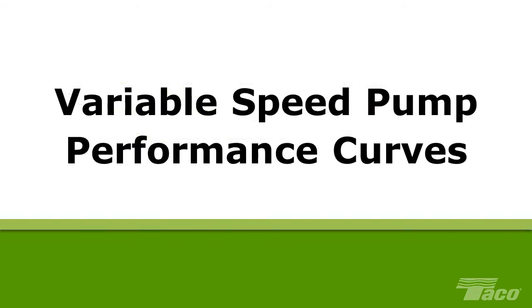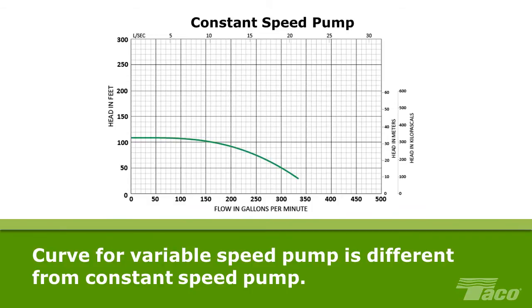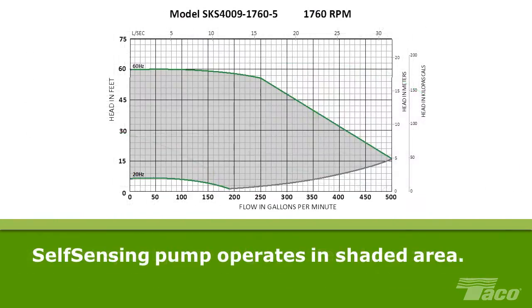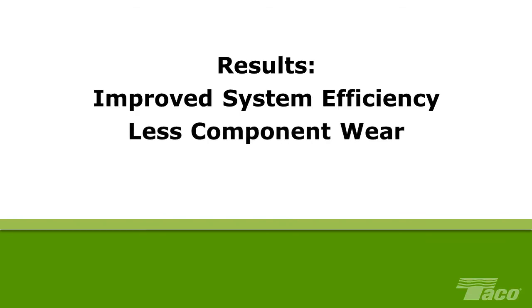Variable Speed Pump Performance Curves. The performance curve for a variable speed pump is significantly different from that of a constant speed pump. Where a constant speed pump can only operate along its performance curve, a variable speed pump can operate anywhere along the curve or below it. The Taco SKS 4009 self-sensing pump can operate at any combination of flow and head in the shaded area of the graph. By varying its speed, the pump delivers the precise combination of head and flow the system requires at any given moment, resulting in improved system efficiency, less wear on components, and reduced energy consumption.